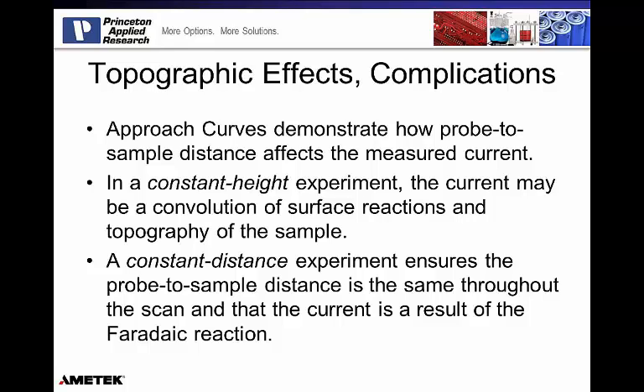experiments. Now, if your sample is polished flat and not tilted, the constant height experiment can make these measurements for you. But if you have more complex geometries with curved samples or sensors that may have some topographic character to them, this is where we're going to need some way to measure constant distance, save that as almost like a background file, and increment that probe in Z as it goes across the plane above the sample surface.